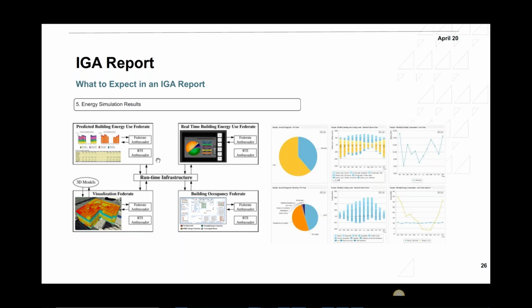And then I would calibrate the building to the baseline year. So I would input everything I know about the baseline year - how things are being operated, what were the set points, what equipment is there - and I would simulate the building and get the results, then compare them to the utility bills for that year, for the baseline.